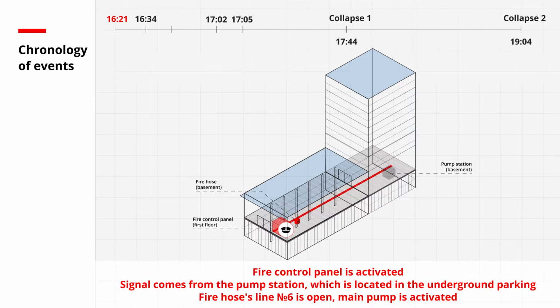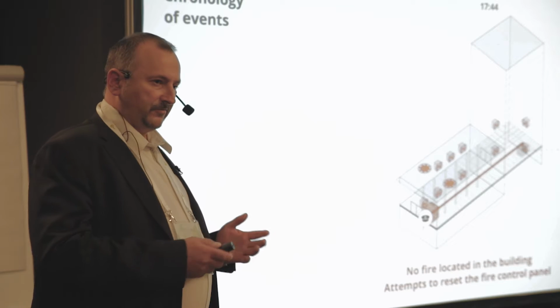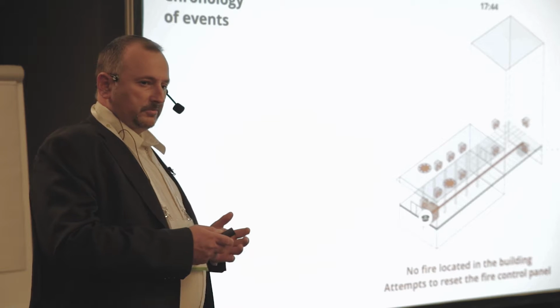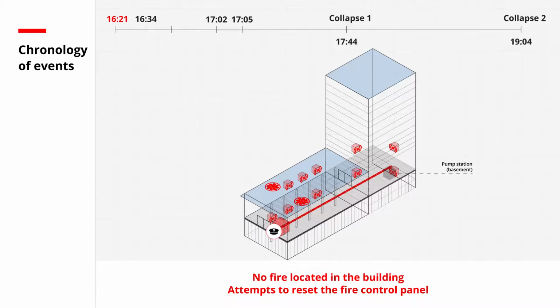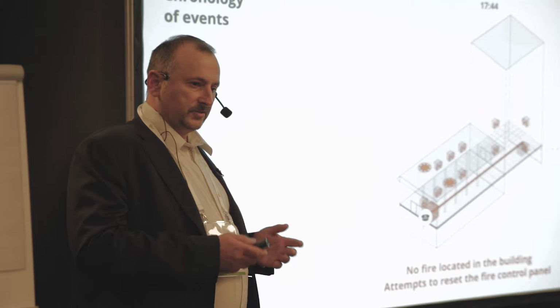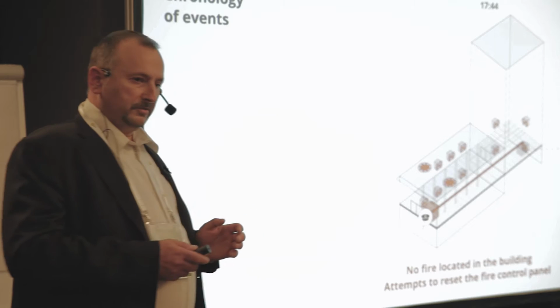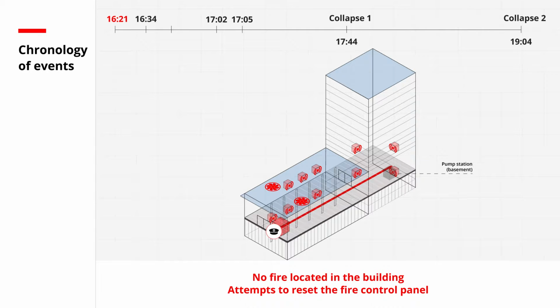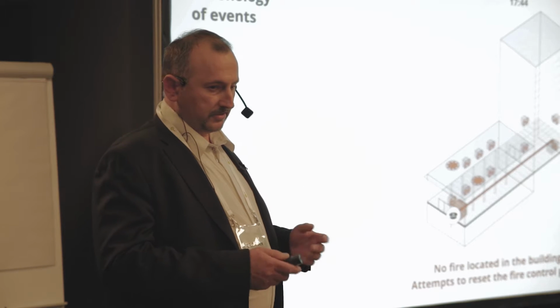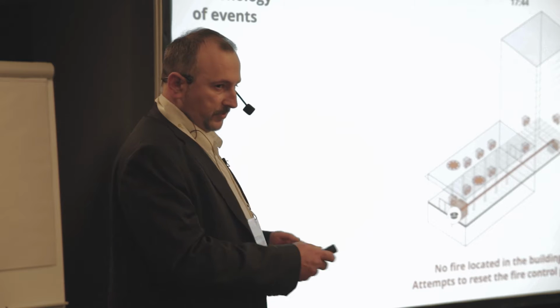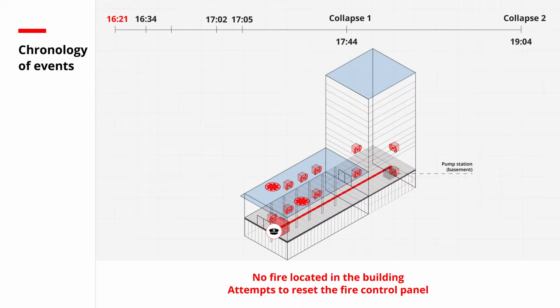The smoke exhaustion system went on, and the normal ventilation went off. But there wasn't any fire inside the building, so it had to be a false alarm. The security attempted to reset the fire control panel several times. Normally it would work, but in case of the pump station, it doesn't work because the valve is still open. The alarm is already existing. Even if you exit the fire alarm mode, it will shortly come again.